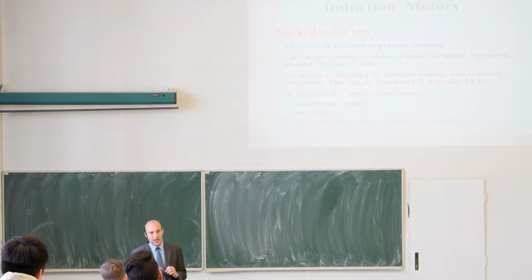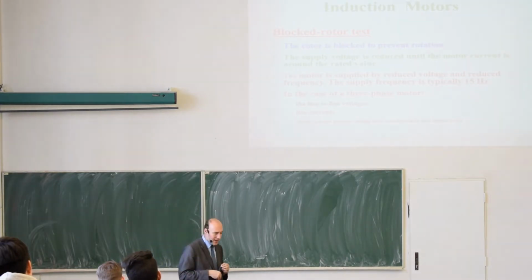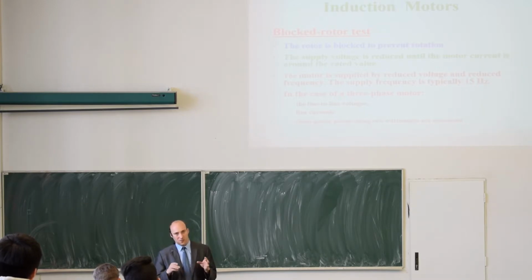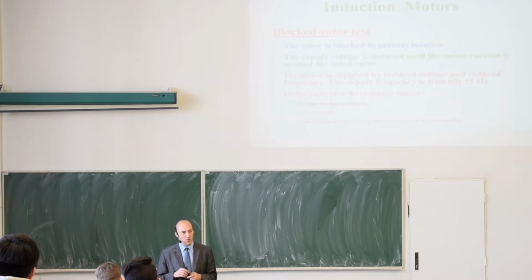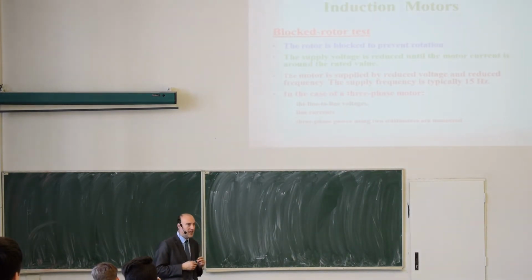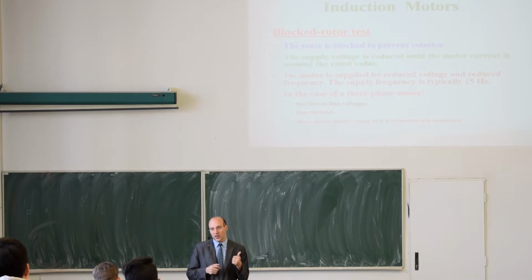So we are reducing the power supply voltage for the motor, and the reduction is done to a smaller current, and typically this test is done for nominal current. In any kind of circuit, we know that the joule losses are proportional to resistance times the square of current. If I want to have the same losses in the circuit, I need to have the same current that corresponds to the nominal current of the motor. So in other words, I will change the voltage during this test only to a very small value so that I have nominal current in the motor.